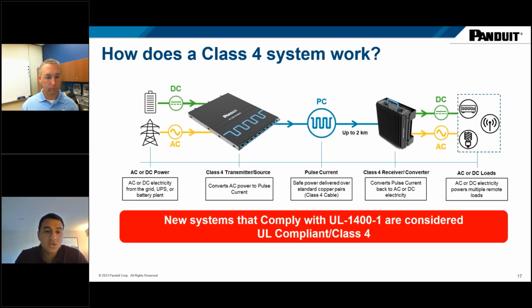You could think of a transmitter or a source residing somewhere in the head end or somewhere central in the building, like an MDF closet. It could be taking DC, it could be taking AC. It's going to convert that into some form of power that is fault managed by the system. In this case, we're showing pulse current flowing through that. It has to be flowing through class 4 cable out to a converter, and you could picture the converter being wall mounted, rack mounted, ceiling mounted. It could take so many different shapes and forms.